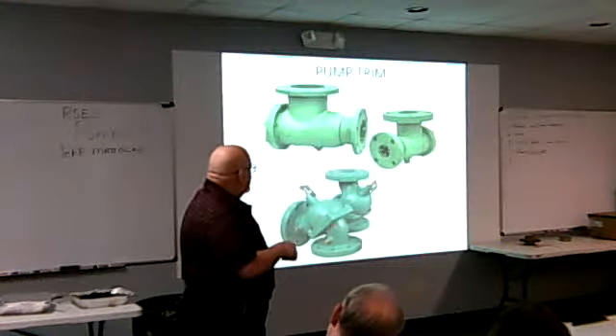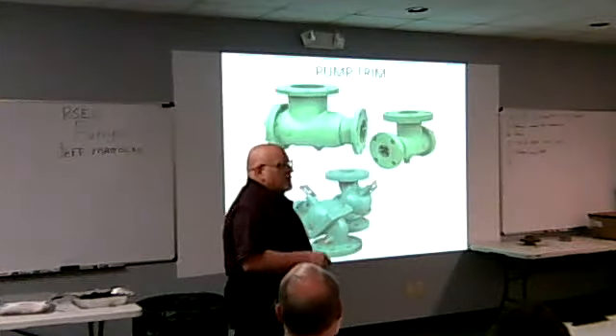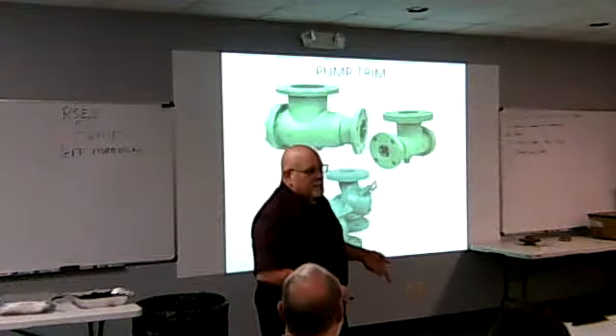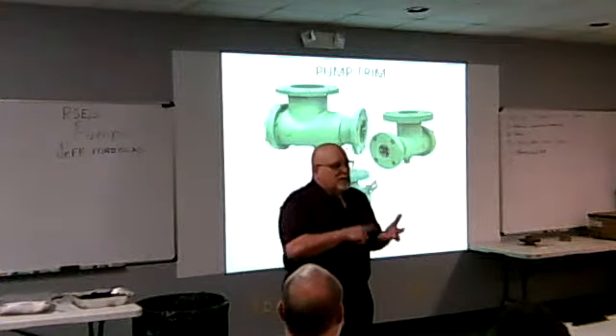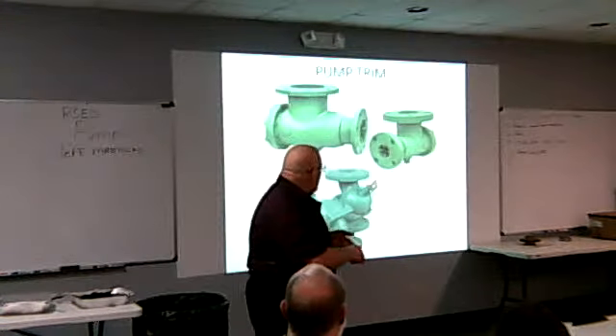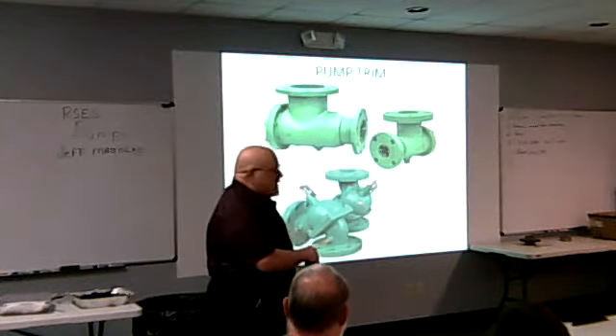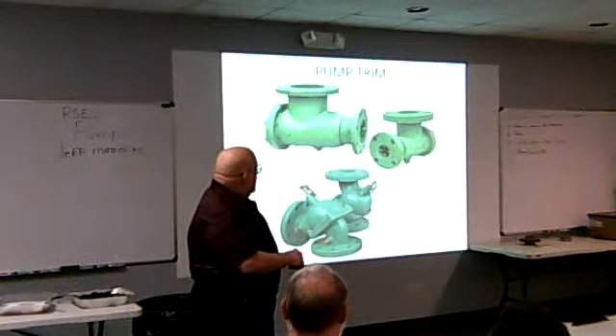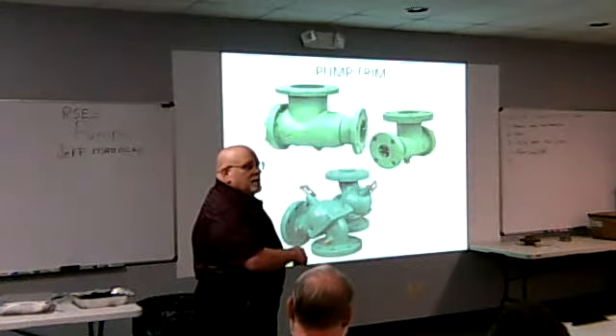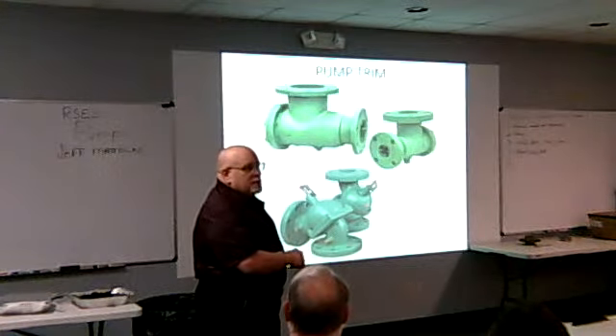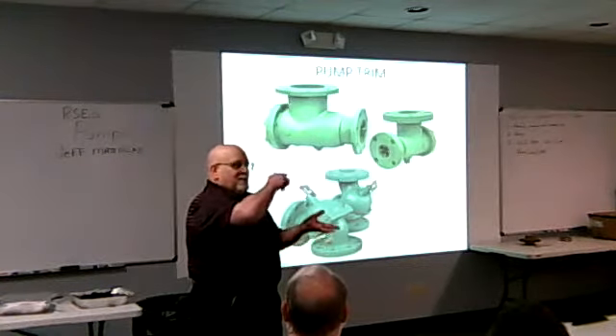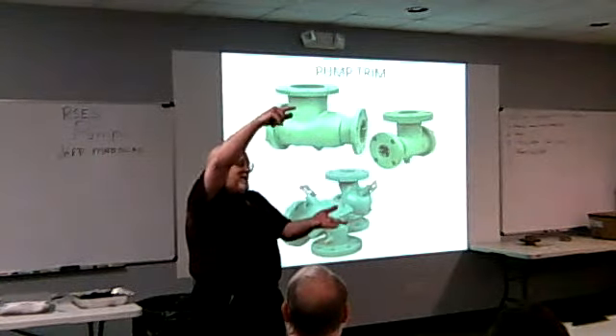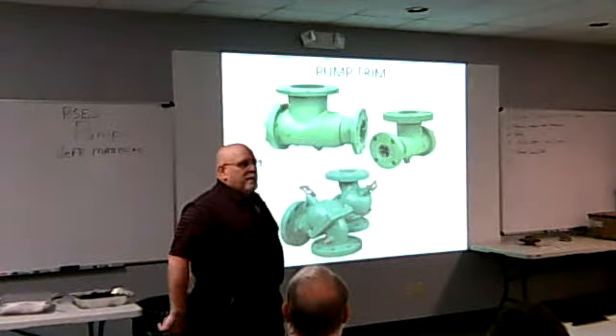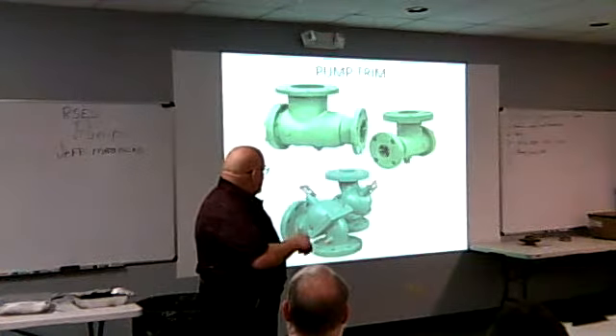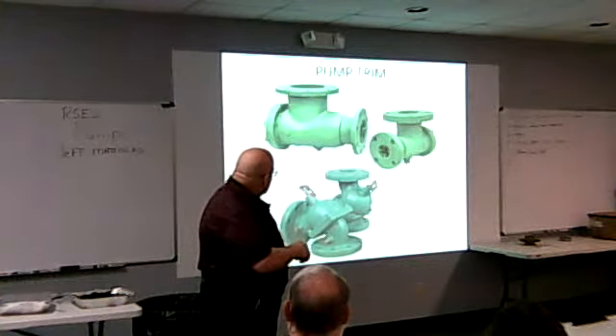And the idea of this is, on every pump discharge, you want a balancing valve, a separate pump check valve, and a shut-off valve. This has all 3. There is an integral check in here. This is your scale for balancing. And it's your 100% bubble type shutoff. So instead of having a wafer check and a balancing valve, you use the same stem as your balancing. Actually right here. Then shut off too. Correct.